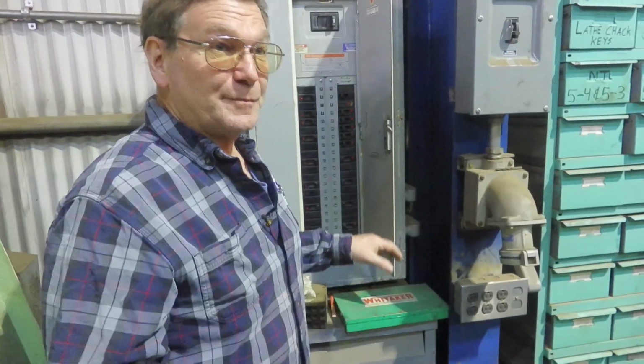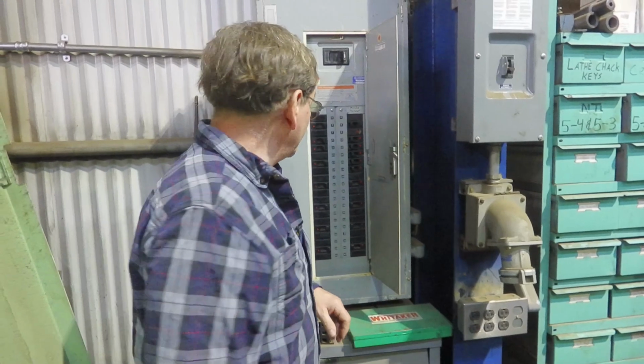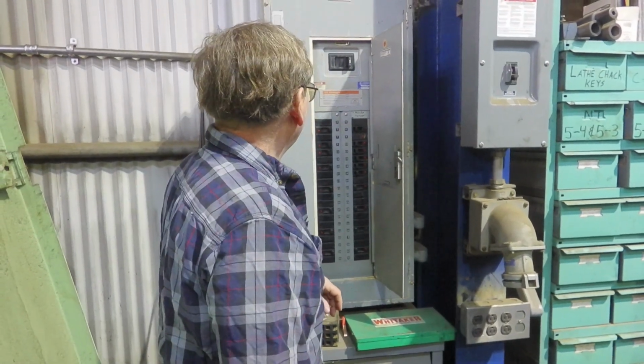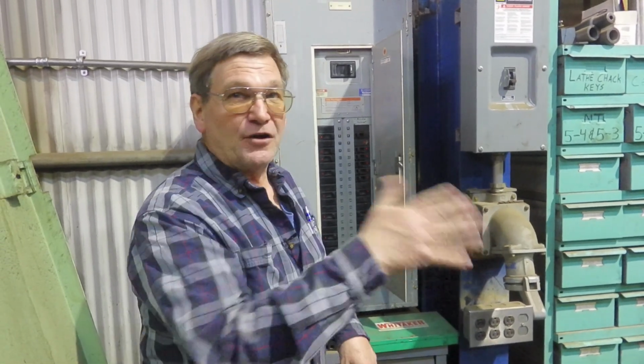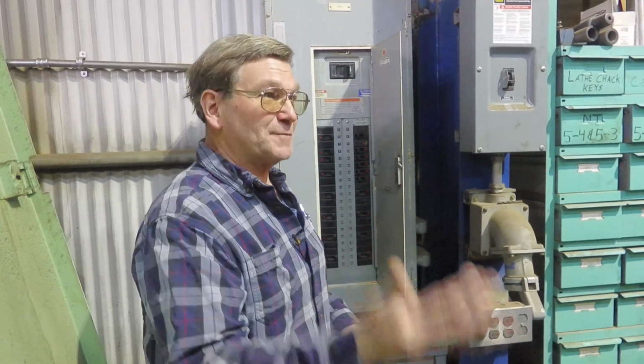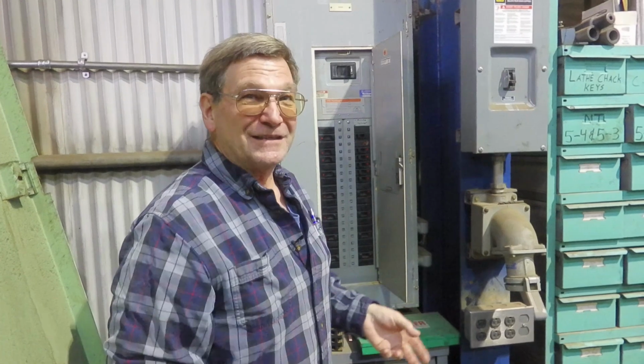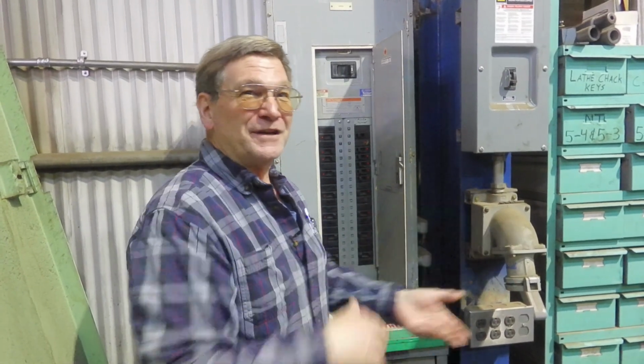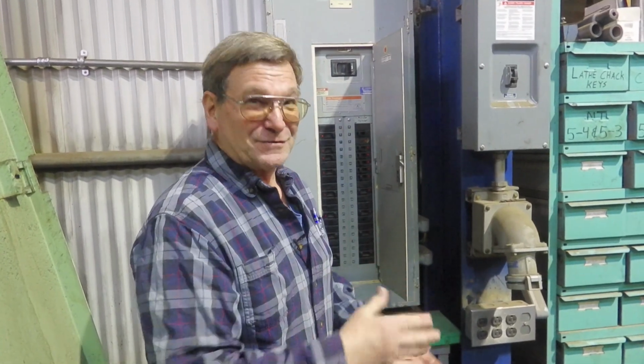A lot of your European equipment, which are CNCs over here, are European based, runs the 380 volt. 380 or 400. They label it both ways these days. Used to always say 380, and then that's plus or minus 20%, which leaves you at the 400. I don't know why they've started calling it 400 now when it doesn't quite make 400, and anywhere in that range of 360-ish, 370 on up to 400 works.